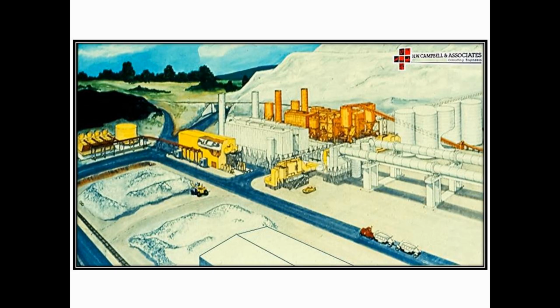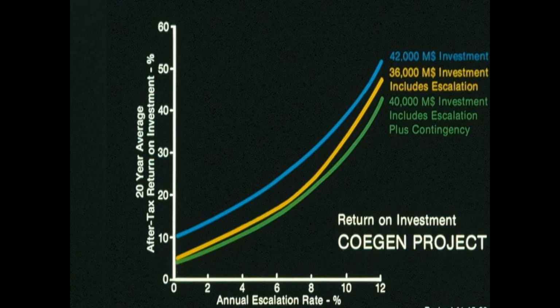When the decision was made to utilize coal as a fuel to raise steam for electrical power generation, the air pollution aspect was cause for much concern. 2 choices were available with regard to boiler design. The first choice was a conventional pulverized coal-fired boiler. The second was a relatively new concept in coal-fired boiler technology called fluidized bed combustion. Detailed investigation to determine which technology would best suit the project was undertaken. The pollution control aspect played a very key role in the final decision. A visit to an operational fluidized bed facility helped convince our engineers that the fluidized bed boiler would be the best choice for this project.